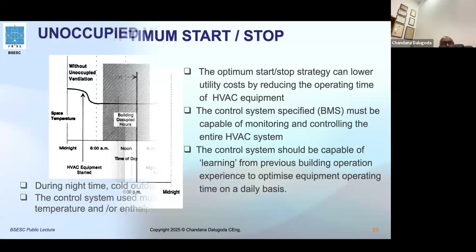Unoccupied ventilation, night purge. This is another function that we should do. Obviously, we have to pre-plan this. AHUs will run in the night for a short period without refrigeration, taking outdoor air into the building, sweeping through the building and exhausting. As you know, outdoor temperatures are plummeting. Now 32, 33, 34 during the day, and it is going down to 28, 26, sometimes ending up at 24 in the late night, morning. So use 24 degrees C air and pre-cool the building.